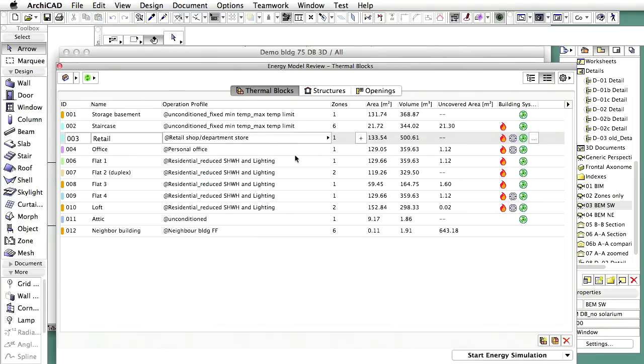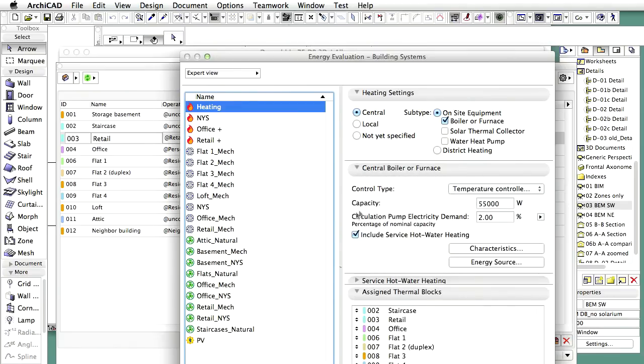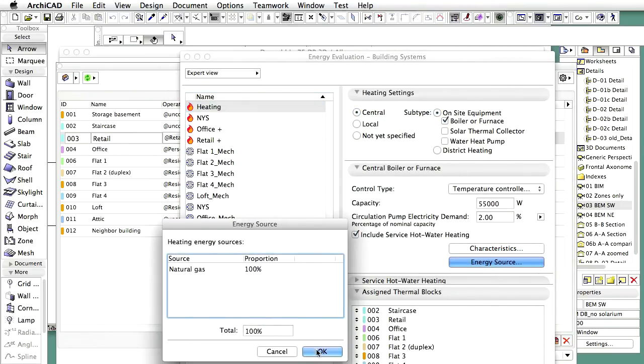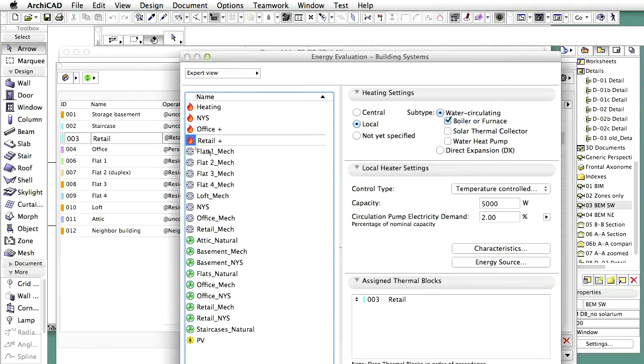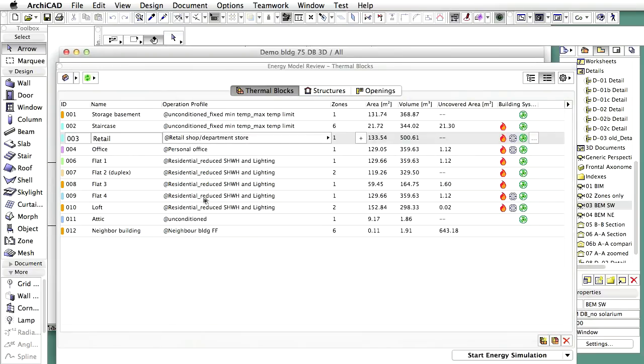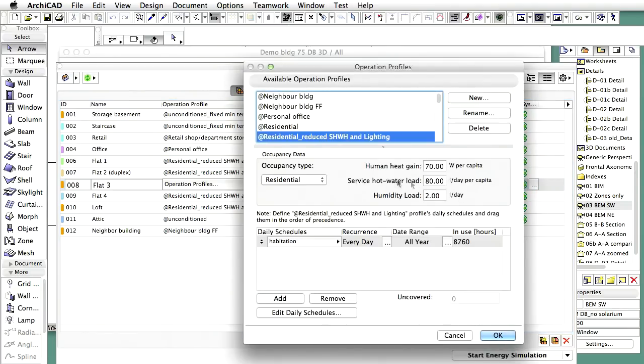Use the Thermal Blocks page of the Energy Model Review Palette to create and configure building systems and add them to the thermal blocks. A central on-site heating system is specified for all thermal blocks that require heating — using natural gas. Two additional smaller local backup gas boilers are provided, one for the office and one for the retail thermal blocks. By using more advanced taps and household appliances, it is possible to reduce the service hot water load by 20% compared to the baseline building. The designed building's energy model contains fewer cooling machines than the baseline building because some apartments do not require mechanical cooling due to effective solar shading.